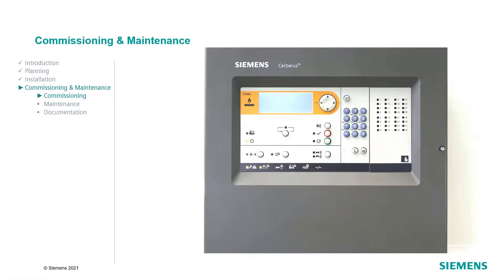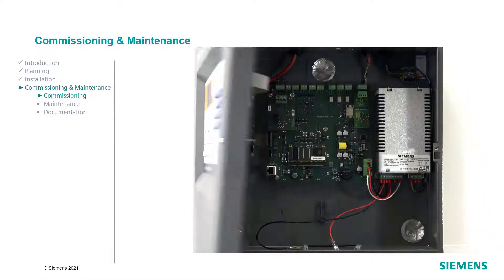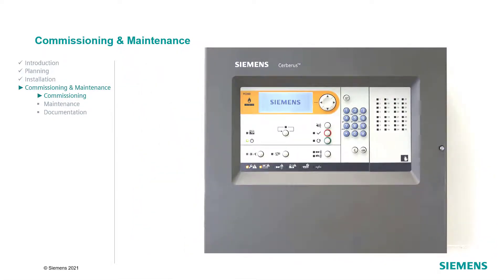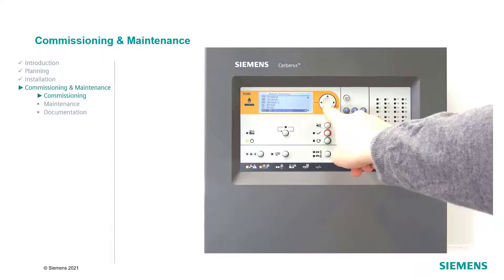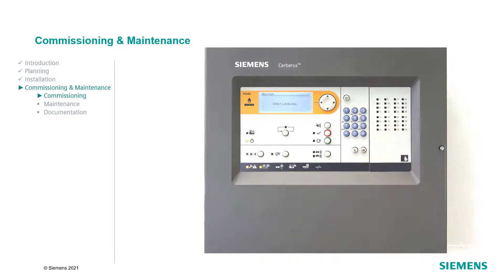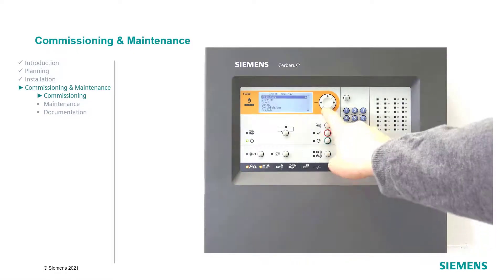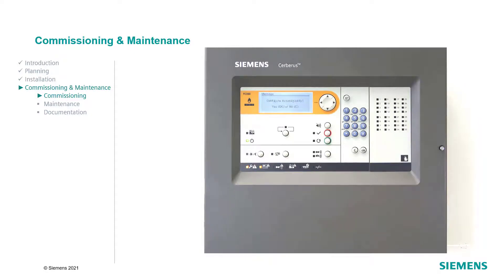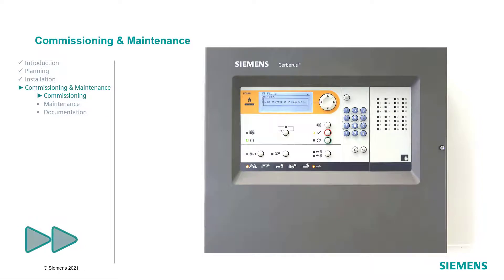Next, let's take a look at the auto-configuration of the panel. Power up the panel and deactivate the buzzer with the switch S3. The panel will start up and you will be asked to select your country. Navigate with the arrow keys and confirm your selection with OK. Next, select your language by also navigating with the arrow keys and confirm your selection with OK. Then decide whether the auto-configuration should be carried out during the start-up process. If yes, confirm with the OK button to start the auto-configuration. All devices on the loops or stubs are read in and assigned to zones.